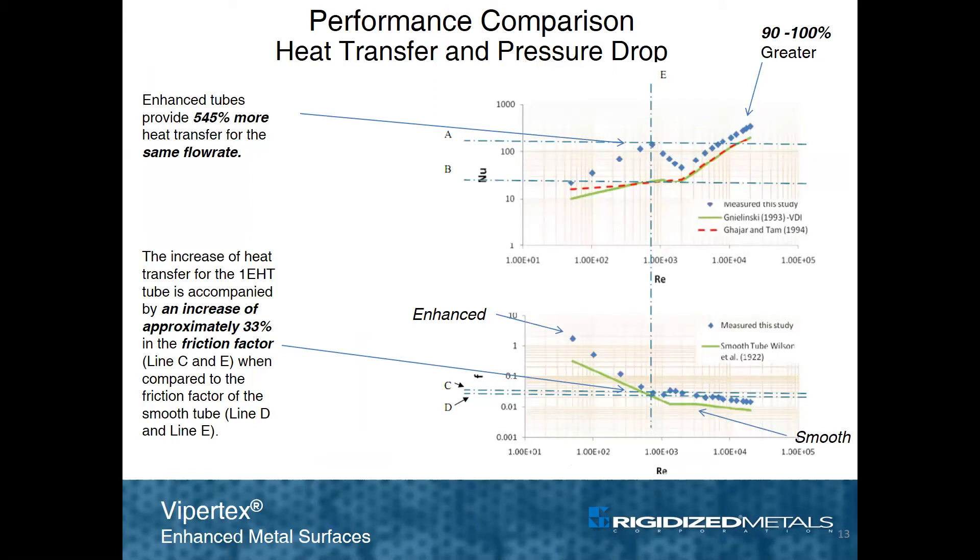The Heat Transfer Research Institute, or HTRI, performs single phase modeling of 1EHT Vipertex tubing. At any flow rate, Vipertex is twice as good as smooth tubing. It is interesting to note that at a lower flow rate, indicated at a Reynolds number of 1000 in the upper diagram, 1EHT tubing produced a 545% increase in heat transfer compared to smooth tube.